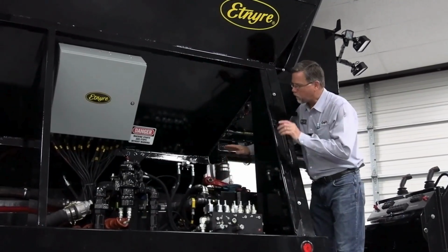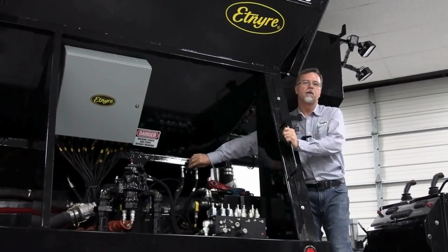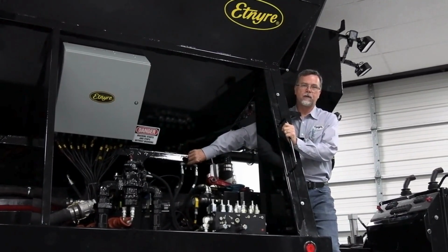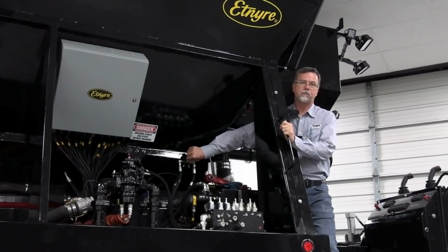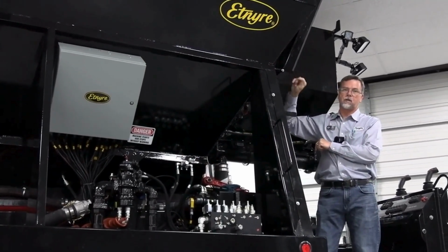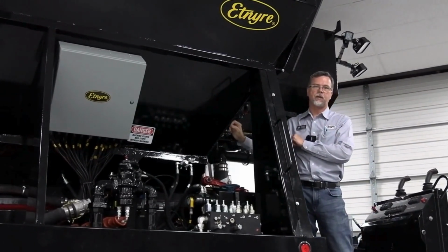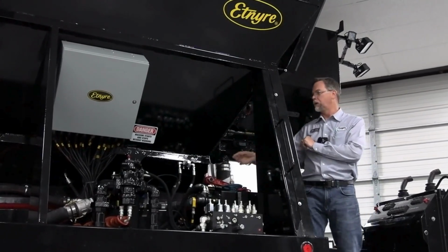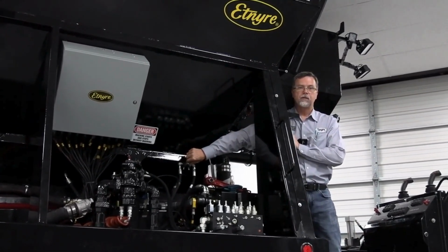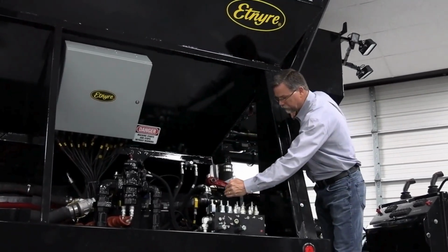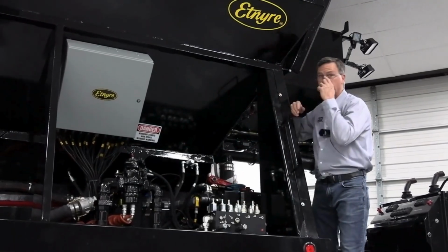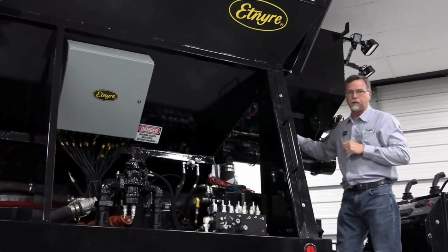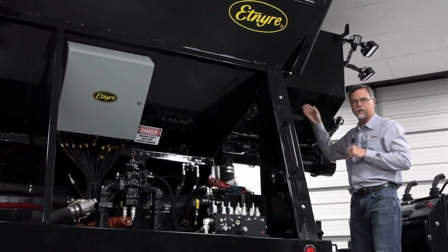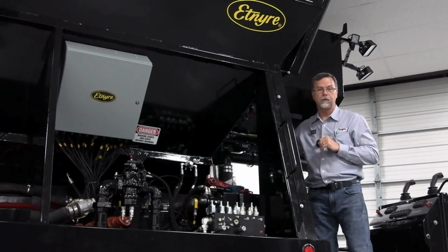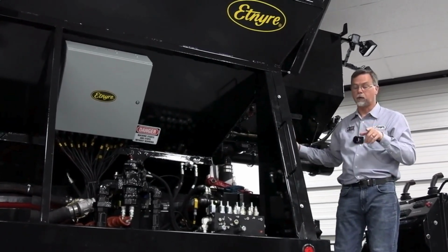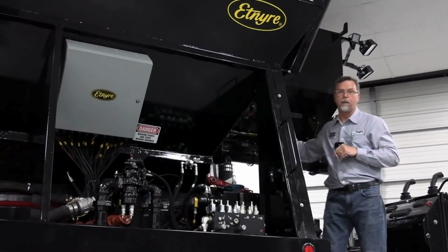At this point, I want to point out this control valve, which is for the fines feeder. It's a needle valve that lets us adjust the fines feeder speed. On the computer screen we see our percentage, and we can dial that in to get the proper percentage of cement dumping into the material. We make that adjustment right here, very simply. That's coming up from the fines feeder circuit, which comes up through here, then to the motor that drives this, and goes back to the tank through the return manifold behind the additive tank on the other side, which we'll get to. This is the control system for managing that speed.